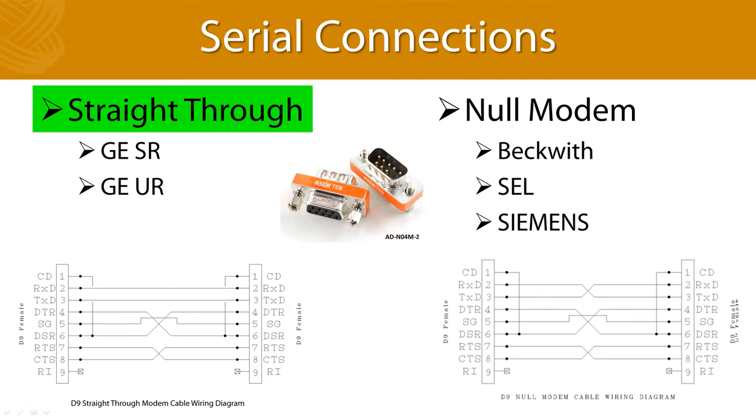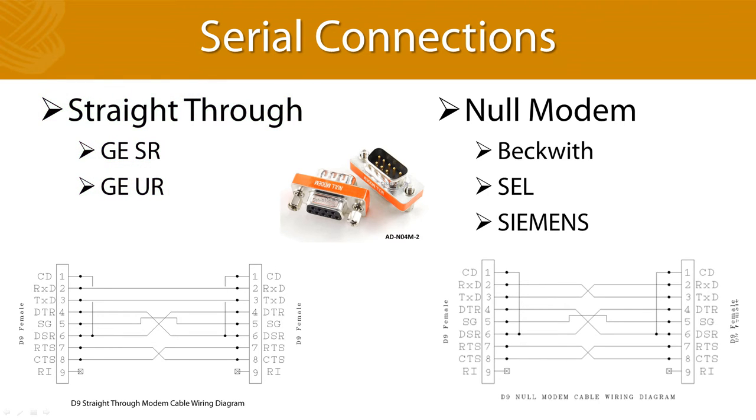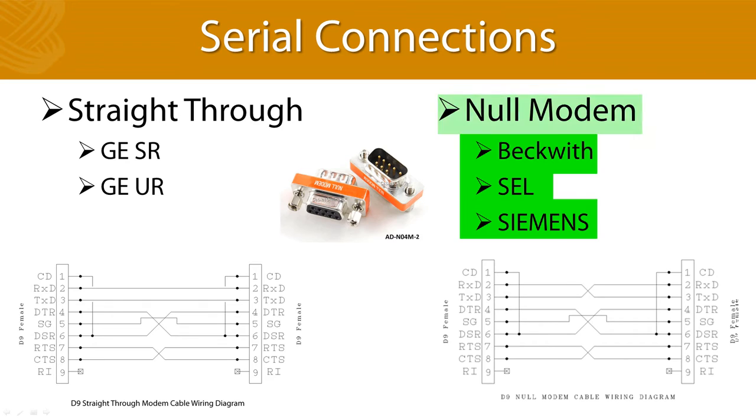You should know what kind of cable is required to communicate with your device. As a general rule, GE UR and GE SR relays use straight-through cables, and pretty much everyone else, including SEL, Beckwith, and Siemens, use null modem cables. This can get confusing because cables often don't have markings indicating what kind of cable they are. You're just supposed to know which cable you bought.